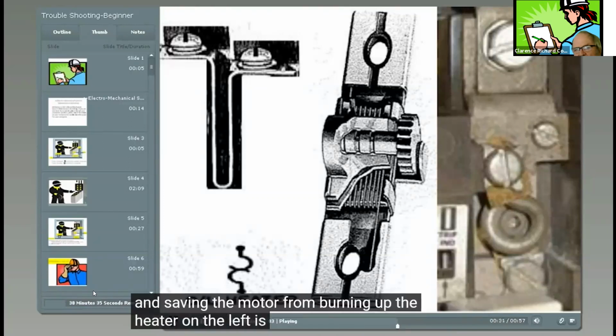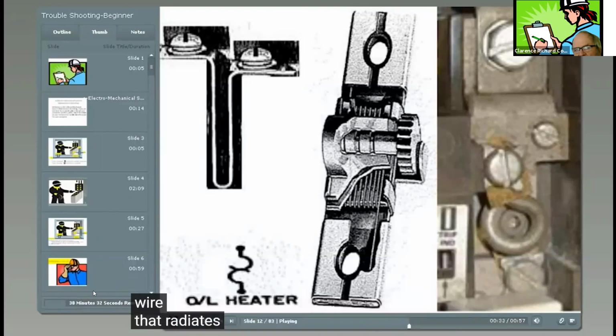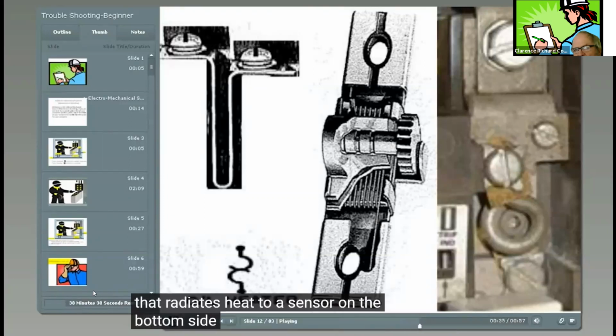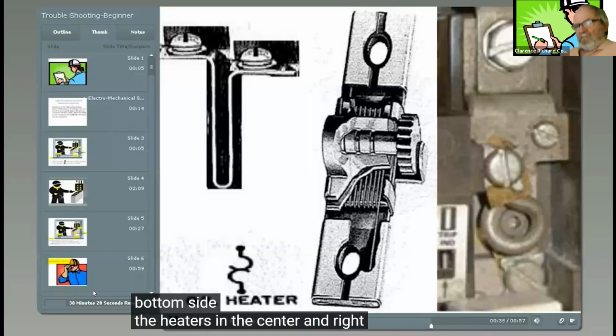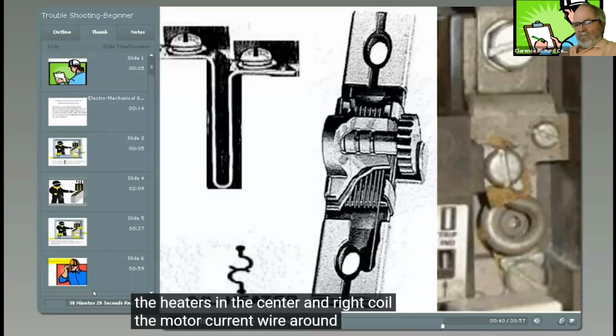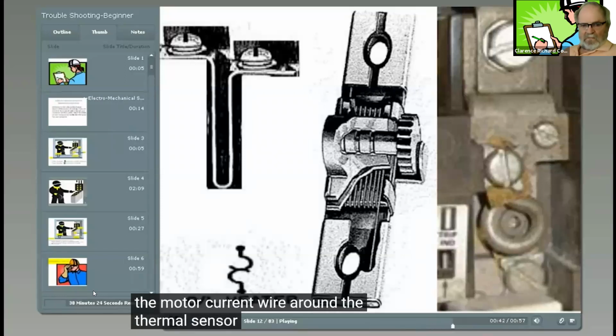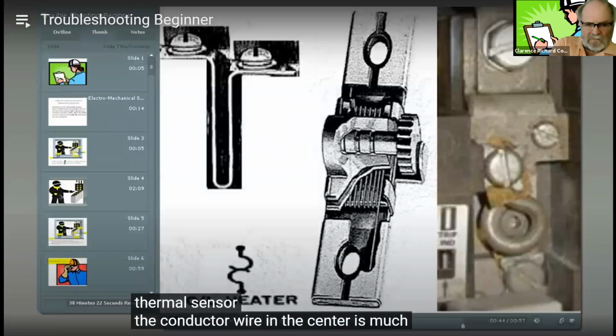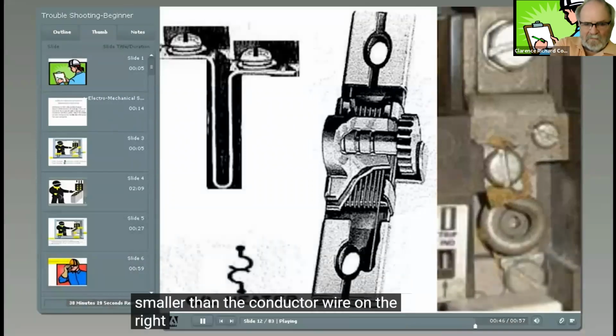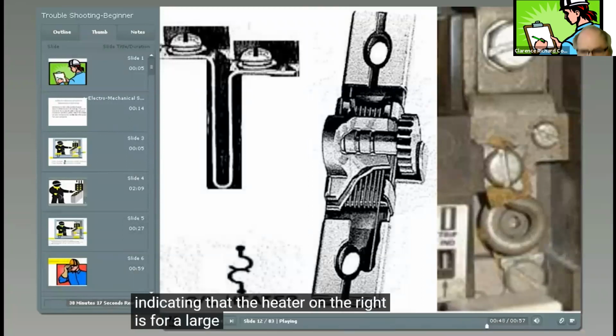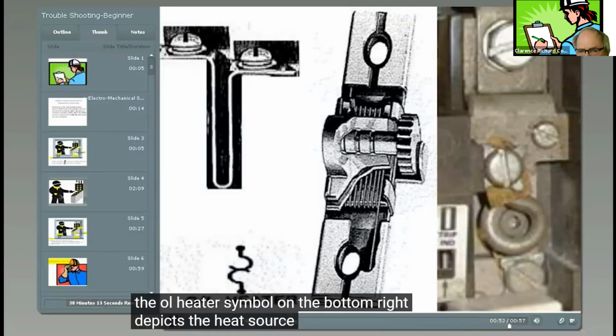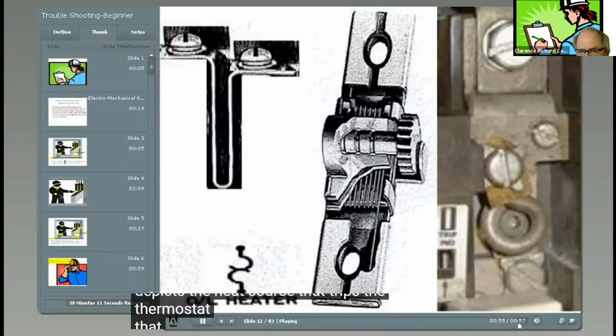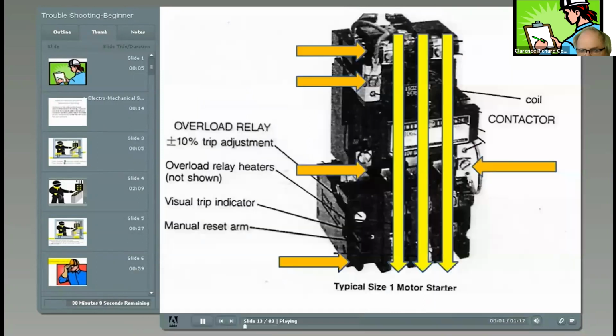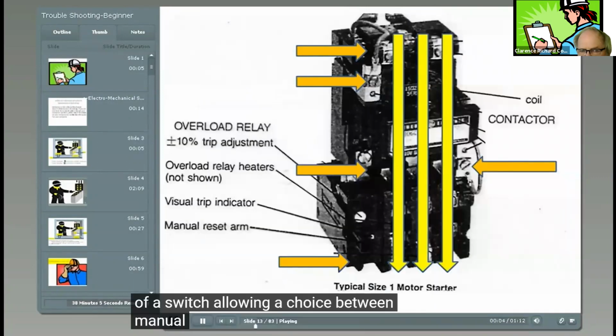The heater on the left is a flat resistive wire that radiates heat to a sensor on the bottom side. The heaters in the center and right coil the motor current wire around the thermal sensor. The conductor wire in the center is much smaller than the conductor wire on the right, indicating that the heater on the right is for a large motor. The OL heater symbol on the bottom right depicts the heat source that trips the thermostat that de-energizes the starter coil. A switch allows a choice between manual and automatic reset.